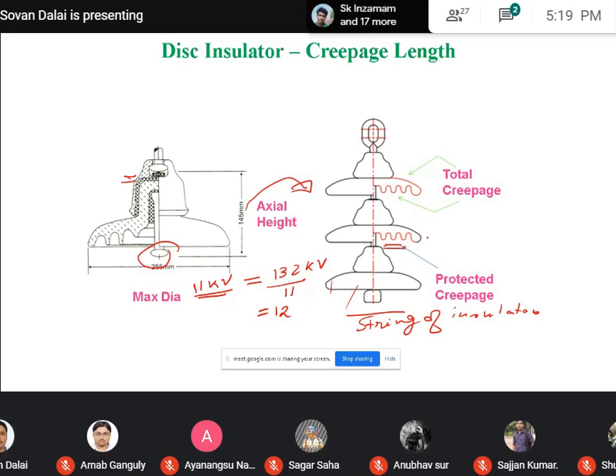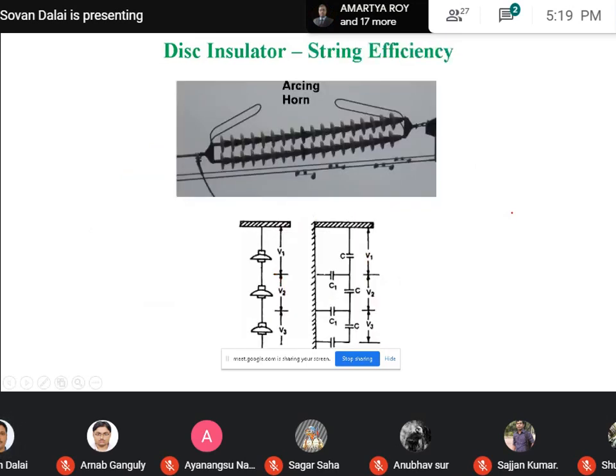The protected creepage distance is basically responsible for the leakage path, which is prominent during wet conditions. Wet condition means during rainy seasons. Most of the rainwater falls on the outer surface, and the portion which comes under the shadow is the portion that withstands the high voltage. In any other conditions, when there is no rain in the outside environment, the total portion holds the system voltage level. Okay. And here you see the number of disc insulators connected in a string.